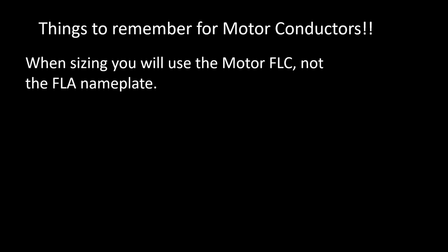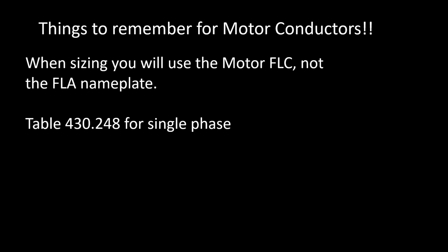So some things that we have to remember is that when we're sizing motor conductors, we're actually going to use the motor FLC and not the FLA nameplate. Now, if they have the FLC printed on the nameplate, then you can use it. But if it's just some amperage stamped on the nameplate, or if it says FLA, then you're not going to be using it. You're actually going to be using the FLC. All right, so when we're dealing with FLC, we have to go to Table 430.248 for single phase. This is assuming that you already know how to do this. If not, I have tons of content teaching you how to use that table. And it's going to be Table 430.250 for 3-phase. So just keep that in mind.